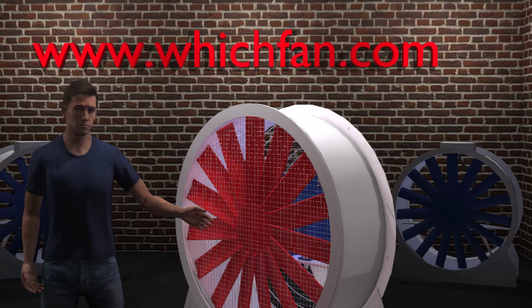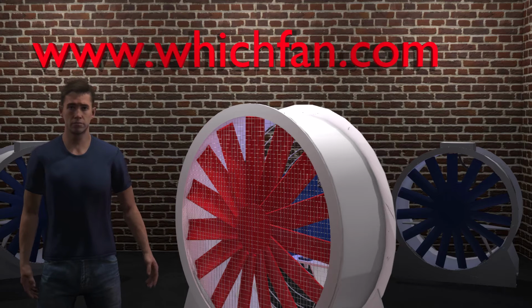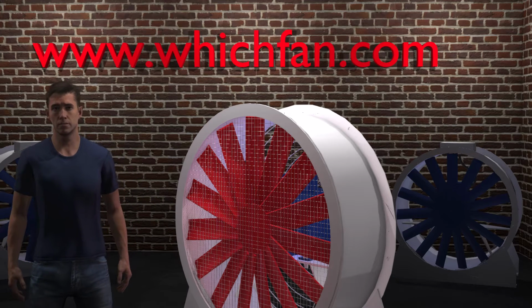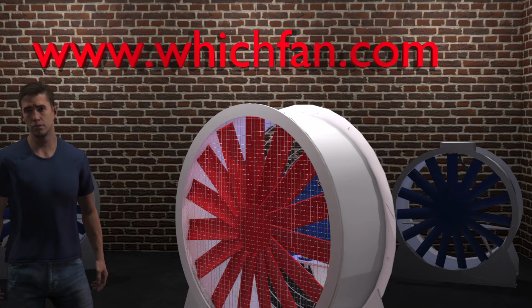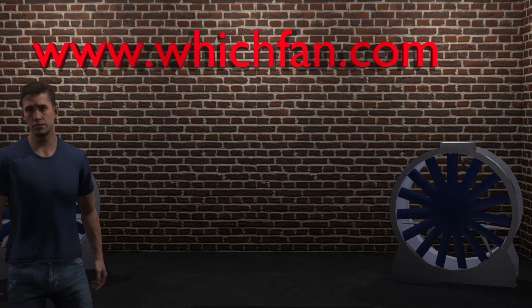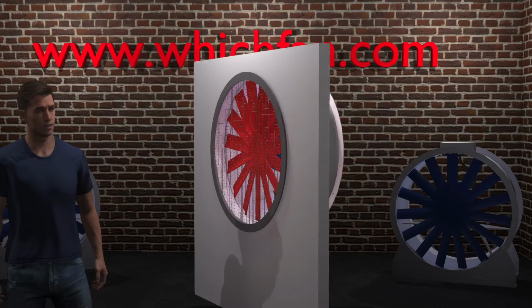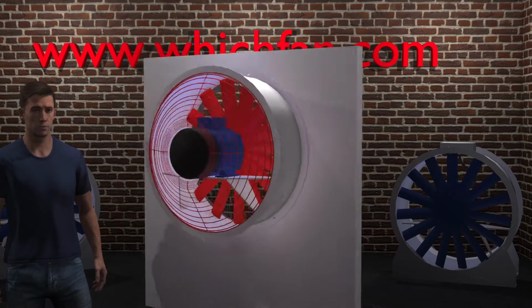Let's look at Form A. This is over the motor, then through the impeller. If you were standing in front of the impeller, the air would be blowing at you. If your fan was bolted against an inside wall, this would be an extract fan, as the air would be blowing out to environment.